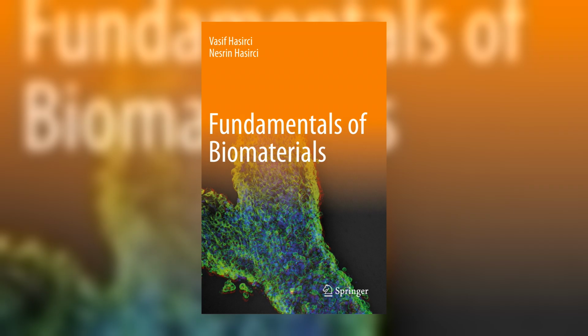This section explains toxicokinetic study design for degradation products and leachables. Every biocompatibility question splits in two directions: what the material does to the body and what the body does to the chemicals. The material sheds. This chapter is the second direction, toxicokinetics, the ADME fate of a leachable or degradation product, meaning its absorption, distribution, metabolism, and excretion. Traced after the other parts of the assessment have already named which species come out.